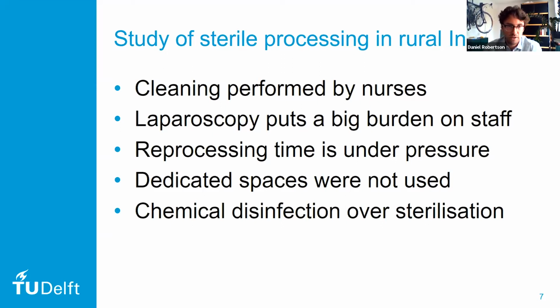And because they're expensive, there's often only one instrument set. So this one set has to be used in one surgery and then be directly used in the surgery afterwards again. And this means that some choices were made in the reprocessing of these laparoscopic instruments in order to be able to use that one set of instruments over again. And that means that a lot of the times chemical disinfection was chosen over sterilization.